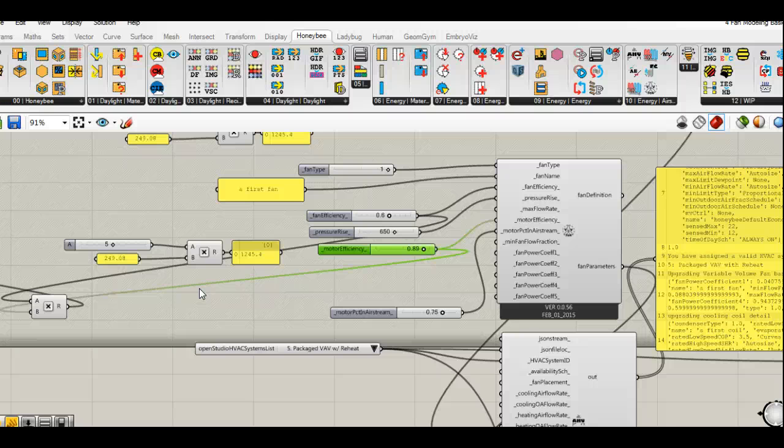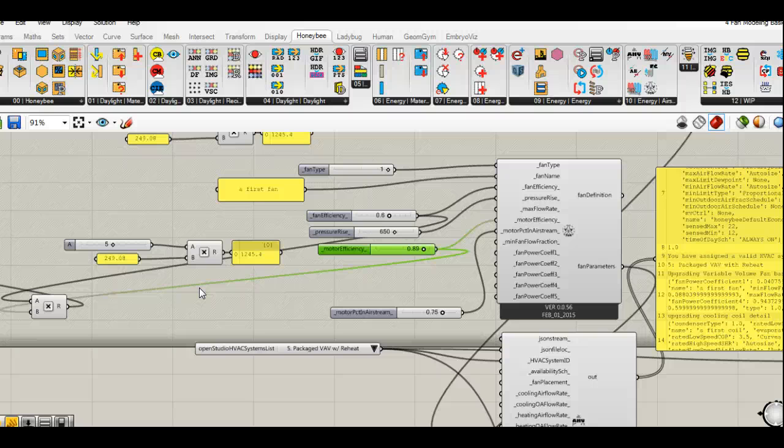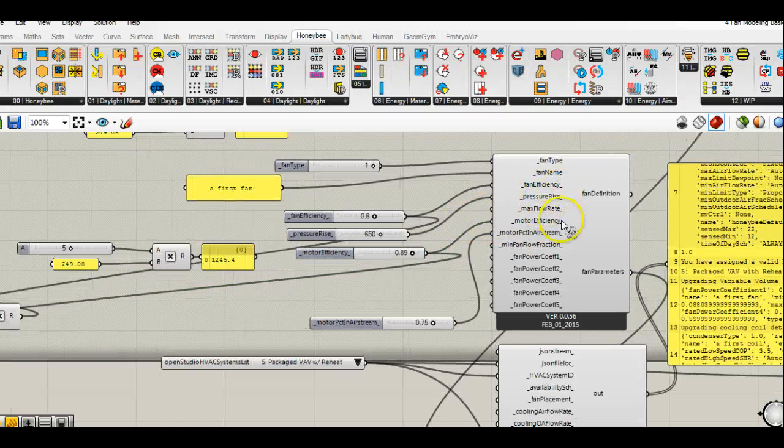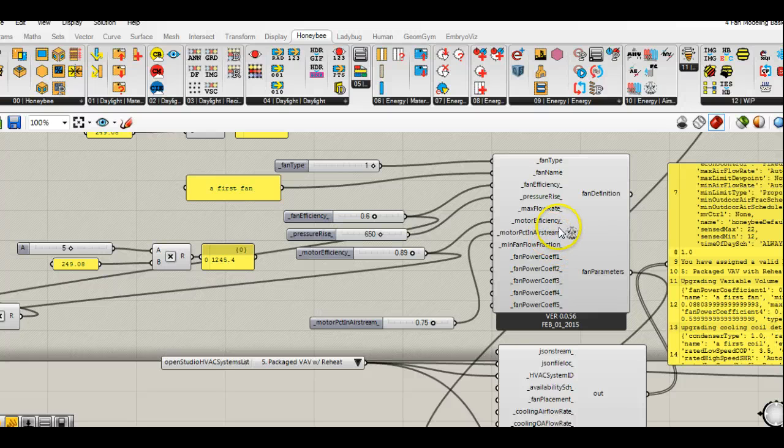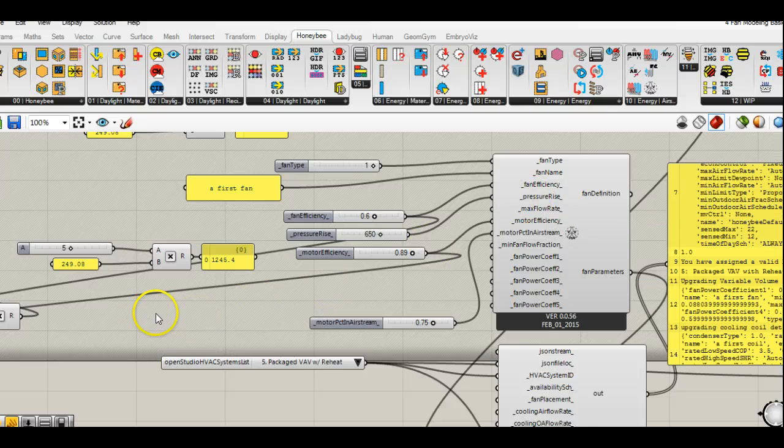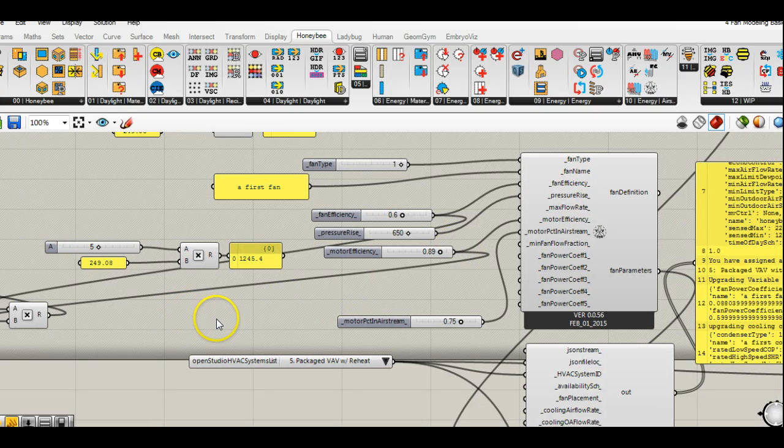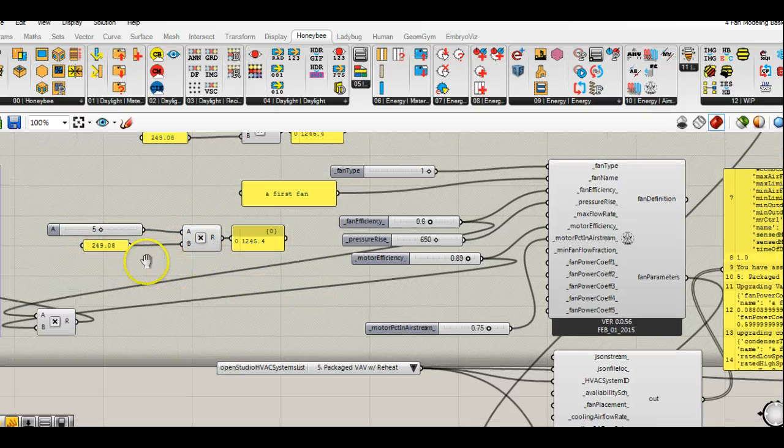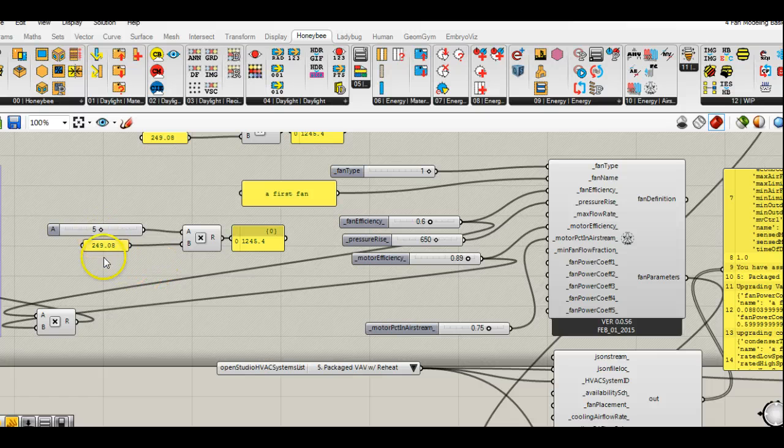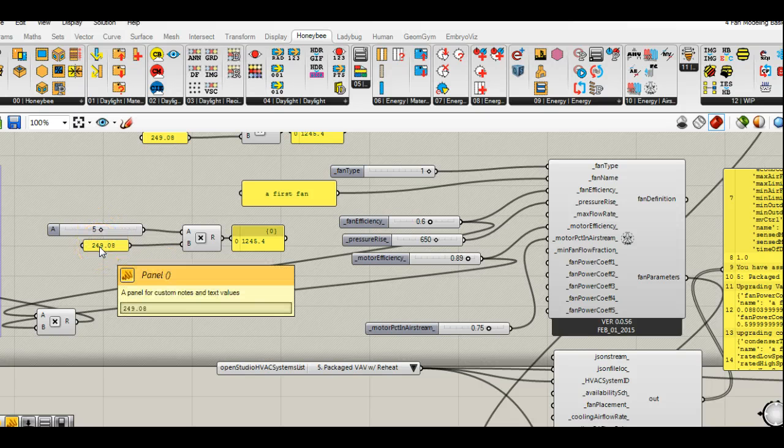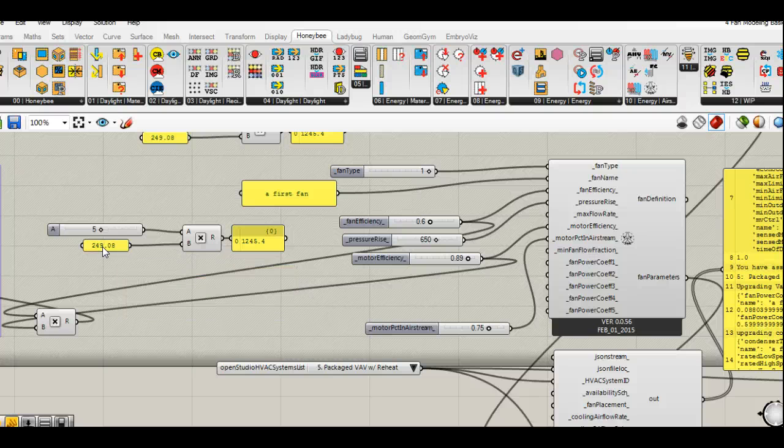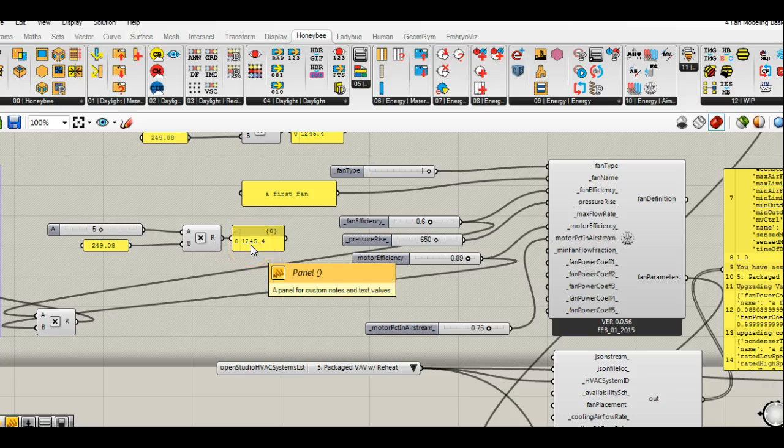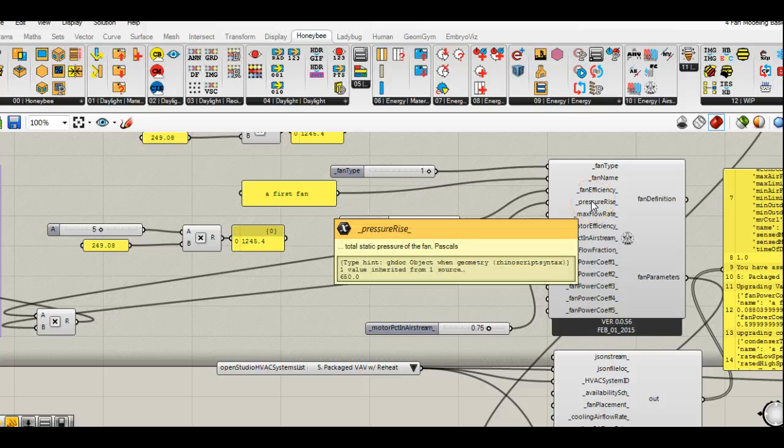In the states, we typically measure that pressure in something called inches of water. Just as a rule of thumb, the inches of water that an entire system will see, both supply and return, will be somewhere around four and a half to five inches of water. The entry that we use for our fan component is actually in pascals. The conversion from inches of water to pascals is 249.08, so I can just multiply the two. You can see here that the resulting pascal is 1245.